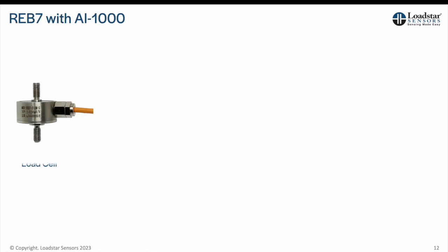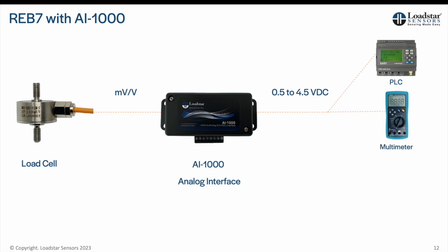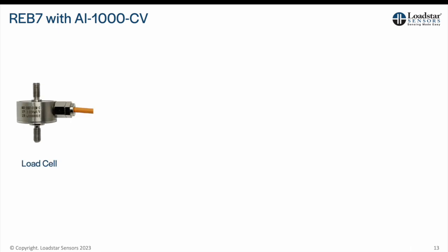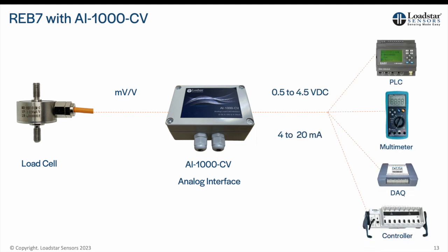If you need to connect to a PLC or data acquisition system, use the AI-1000 analog interface and calibrate the pair. If you need to transmit the analog signal over longer distances, use the AI-1000CV which offers a 4 to 20 mA output option. You can get both a 0.5 to 4.5 VDC as well as 4 to 20 mA calibrated output if needed.